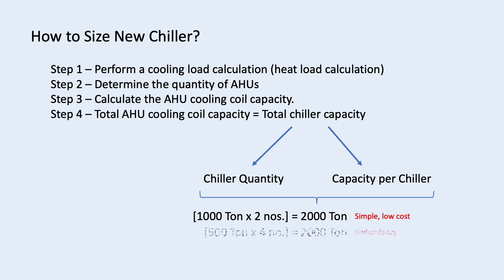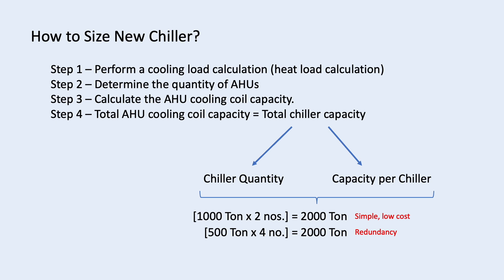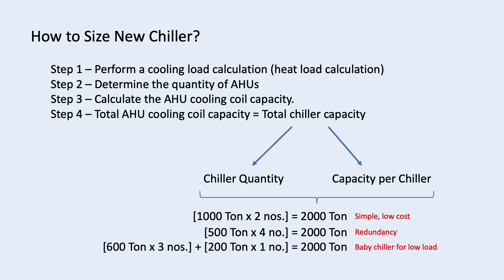Or you can use 4 chillers each with 500 ton. The benefit of having more chillers is you have backup redundancy. In case 1 chiller down, you still have 75% of the total capacity. Another combination is 3 600 ton and 1 200 ton chiller. Big chiller can't operate at very low capacity. You need a baby chiller if you have low load conditions. That's all for this video. Thank you.